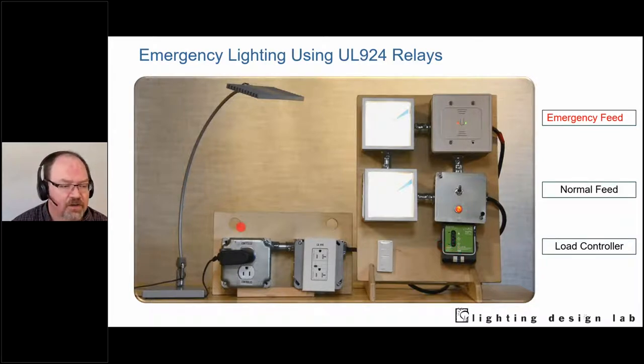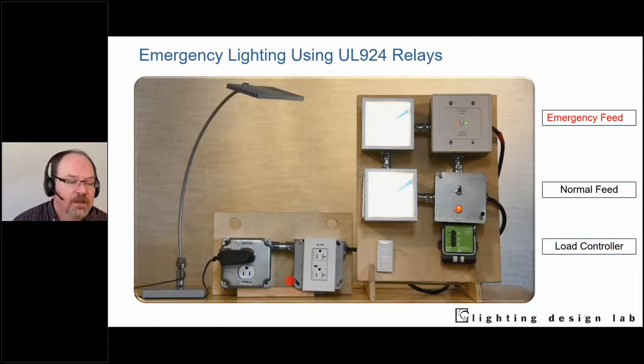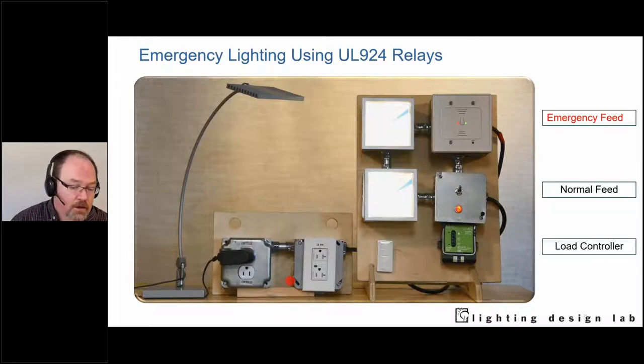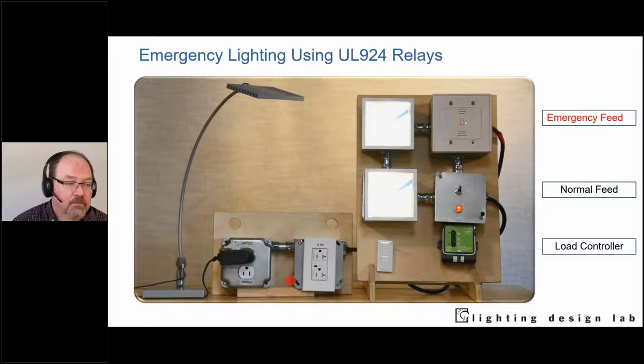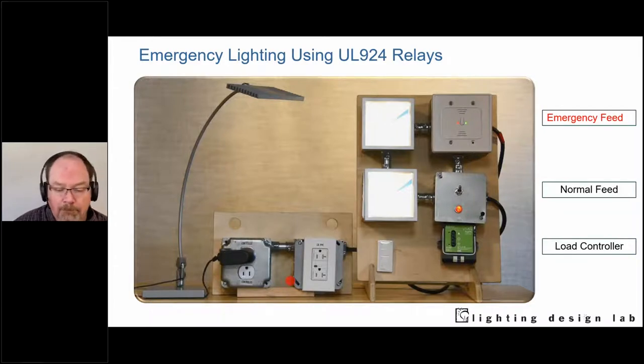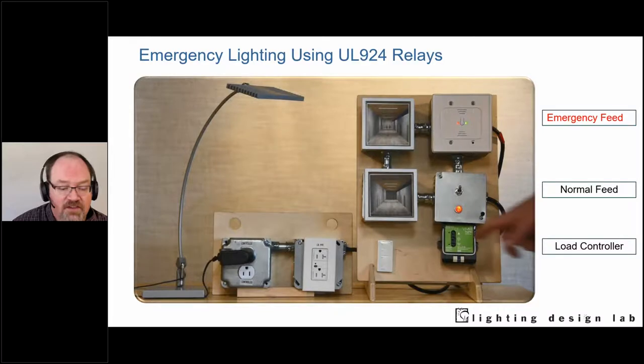Regarding where UL924 is mandatory: UL924 itself isn't mandated by a specific code section per se, but it is a path to compliance. What is mandatory is the ability to turn lights on and turn them off — whether through a comprehensive lighting control system or through luminaires with battery backups that the normal control system operates until power loss triggers battery takeover.